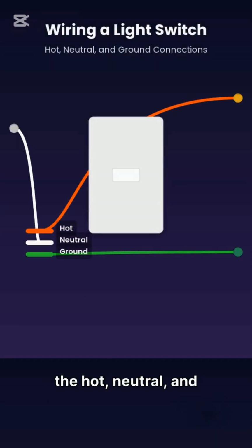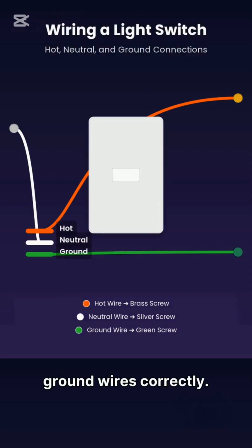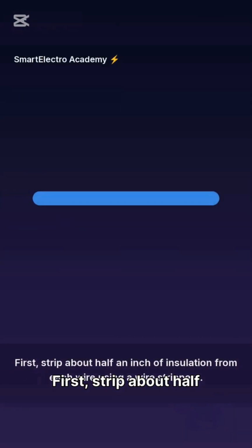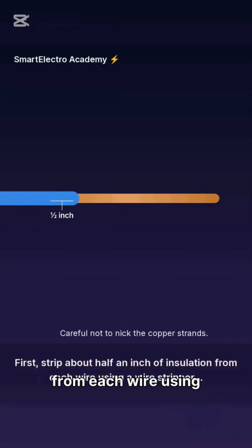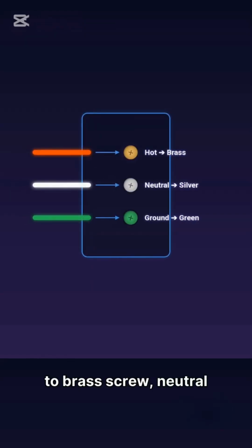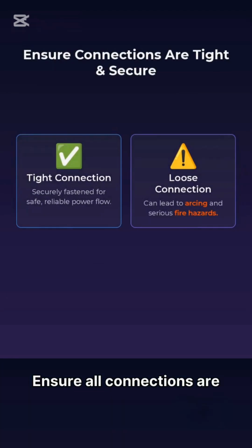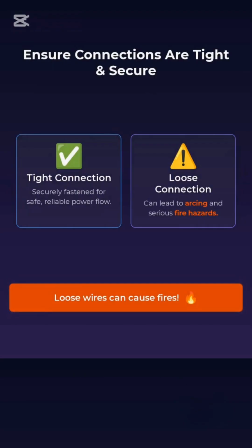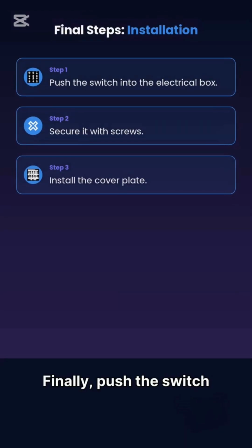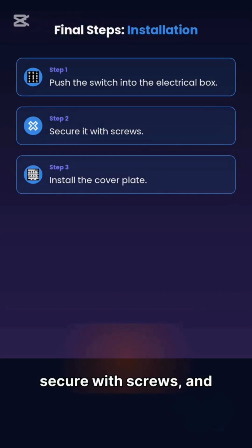Connect the hot, neutral, and ground wires correctly. First, strip about ½ inch of insulation from each wire using a wire stripper. Careful not to nick the copper strands. Next, connect hot wire to brass screw, neutral to silver screw, and ground wire to green screw on the switch. Ensure all connections are tight and secure. Loose ones can lead to arcing and fire hazards. Finally, push the switch into the electrical box, secure with screws, and install the cover plate.